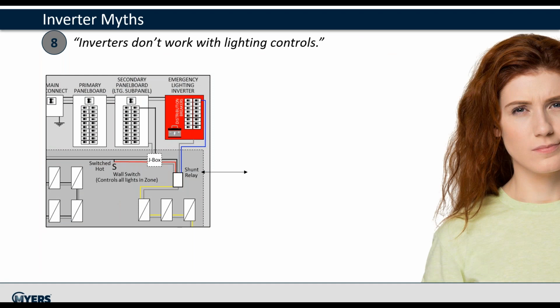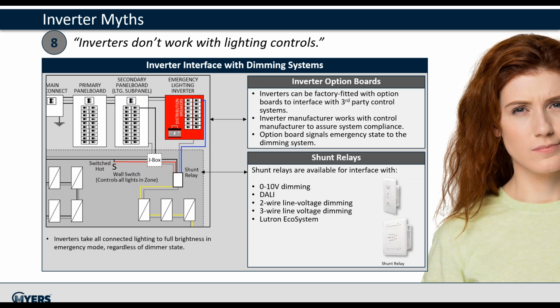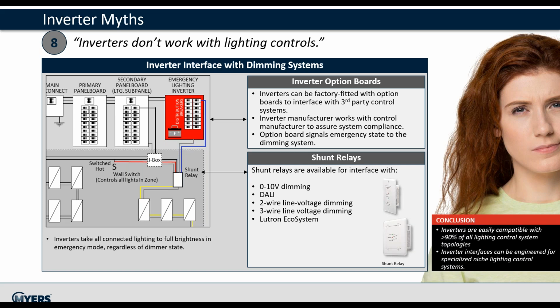Inverters do not work with lighting controls. For the smaller inverter systems, the basic controls that would traditionally be built outside of the inverter system can be included as options. These include shunt relays, switch circuits, 0 to 10 dimming controls, and controls to third-party systems. For larger systems, shunt relay and transfer switches tie into the inverter system, providing the local controls required so that a subset of the normal lights can also function as the emergency light with minimal additional effort.